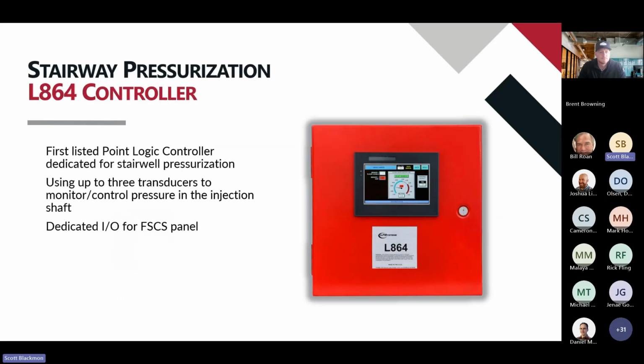The panel itself has a 7-inch touchscreen. It's basically listed for and certified to UL 864. The entire system is. One of the nice features about this is it's got a dedicated I/O for the FSCS panel, also for the fireman's pull. It also allows you to do your weekly or monthly testing without actually activating the entire system.